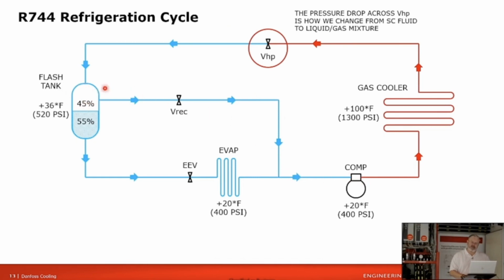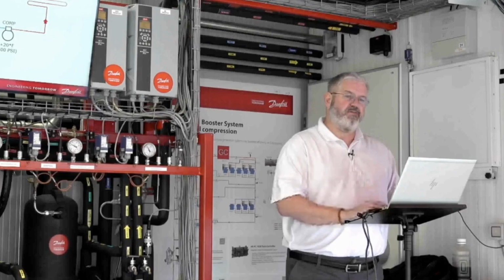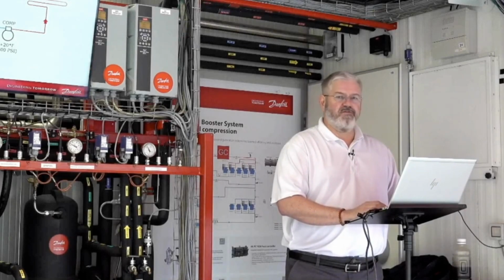Dealing with that flash gas coming across the high pressure valve is why the receiver is commonly called a flash tank. I've had people ask me in the past, where's the flash tank? They're thinking there's a second vessel. It's just what people call the receiver on a CO₂ system. It's still just the receiver. We're just dealing with flash gas at this point.